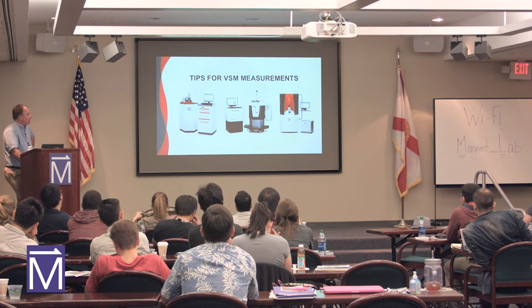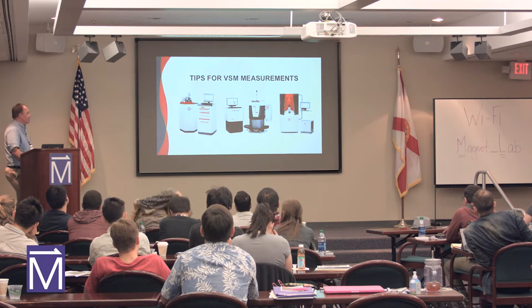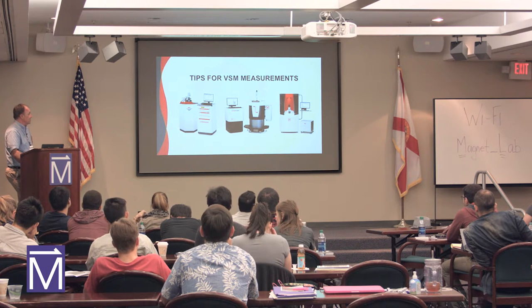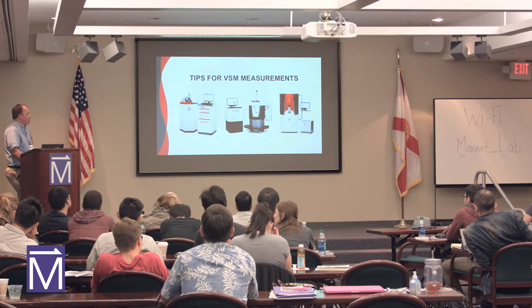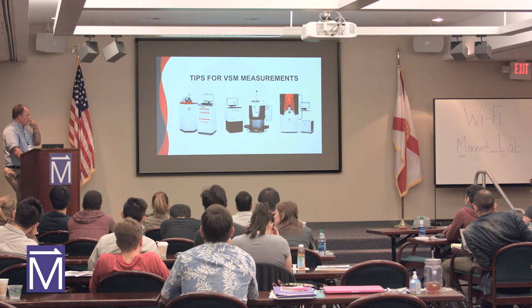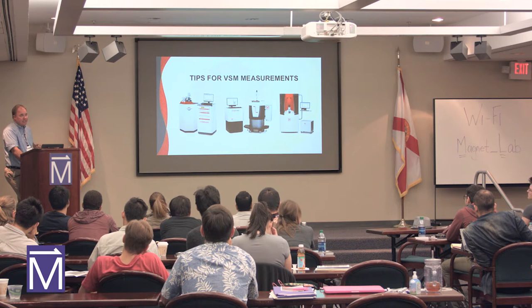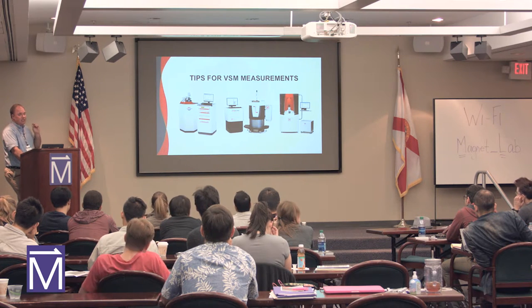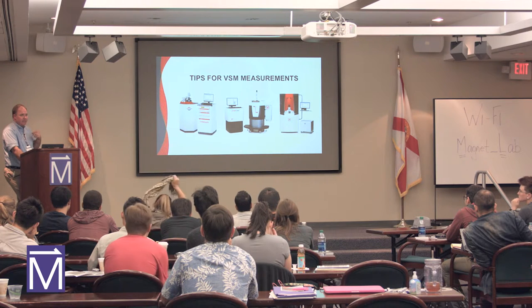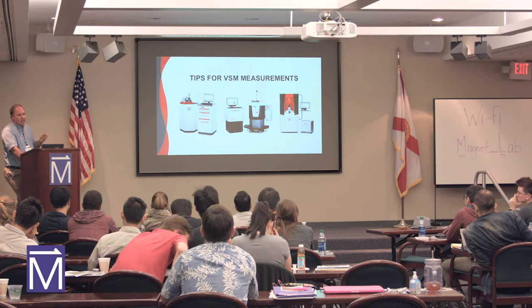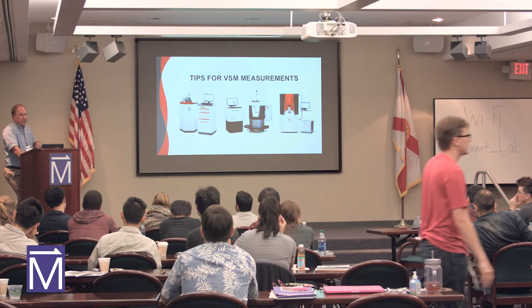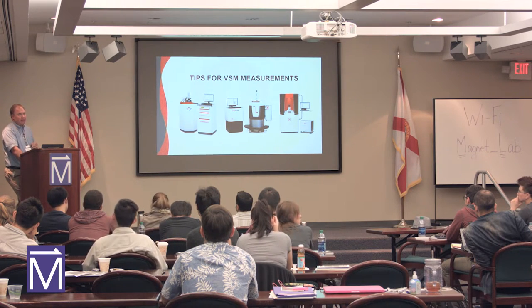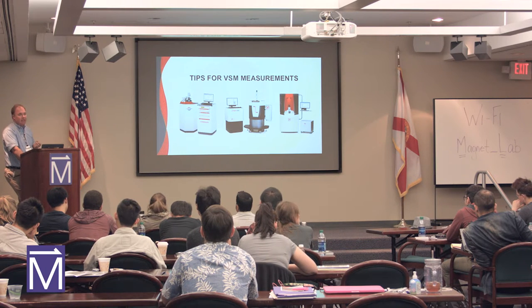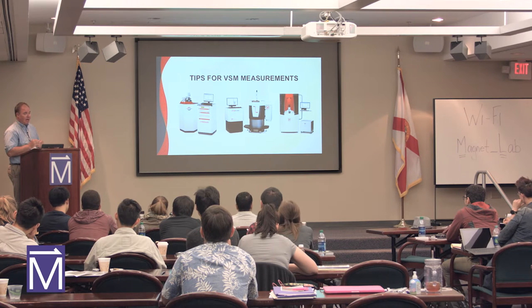And now let's change gears, and we'll talk a little bit about tips for making some of the magnetometry measurements on the systems. So typically you're doing the VSM measurements on the PPMS Dynacool series. The squid magnetometer has a VSM mode to it, but it's using the squid to make the VSM measurement. So typically the squid measurement for the magnetometry for those hysteresis curves is a DC squid type method. With the squid you have 10 to the minus 8 EMU sensitivity. The VSM technique is 10 to the minus 6 EMU. So you've got better sensitivity with the squid magnetometer.